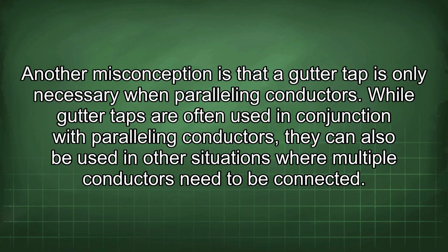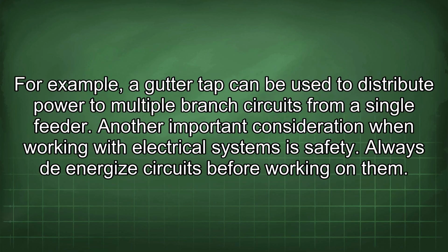Another misconception is that the gutter tap is only necessary when paralleling conductors. While gutter taps are often used in conjunction with paralleling conductors, they can also be used in other situations where multiple conductors need to be connected. For example, a gutter tap can be used to distribute power to multiple branch circuits from a single feeder.